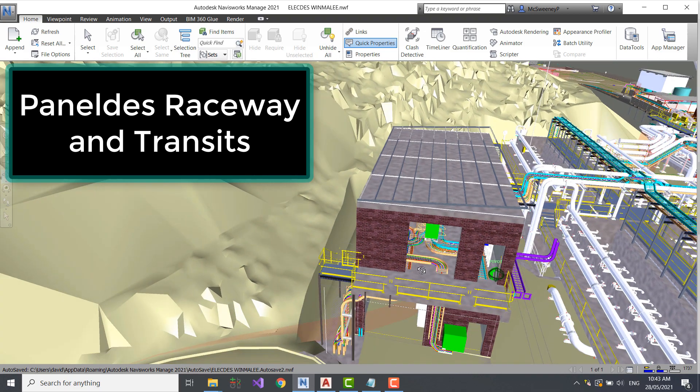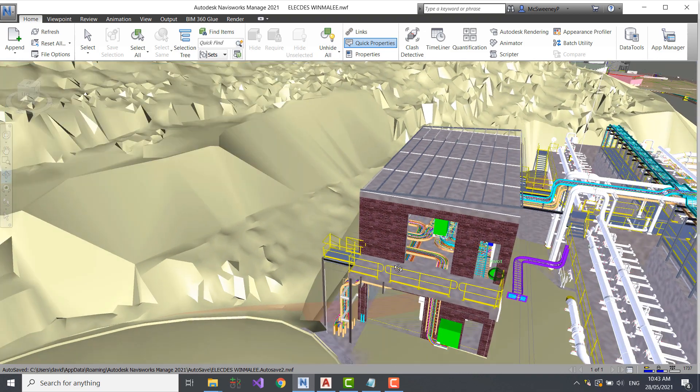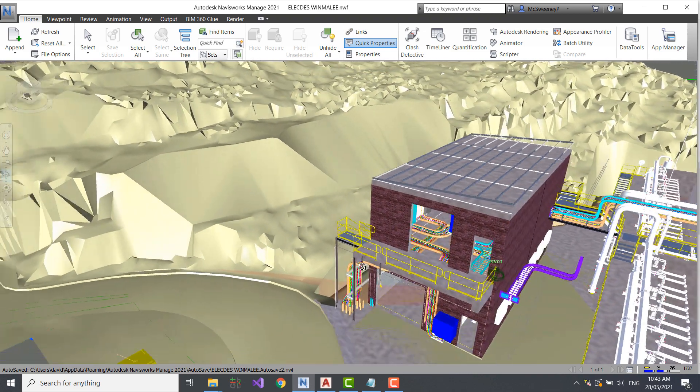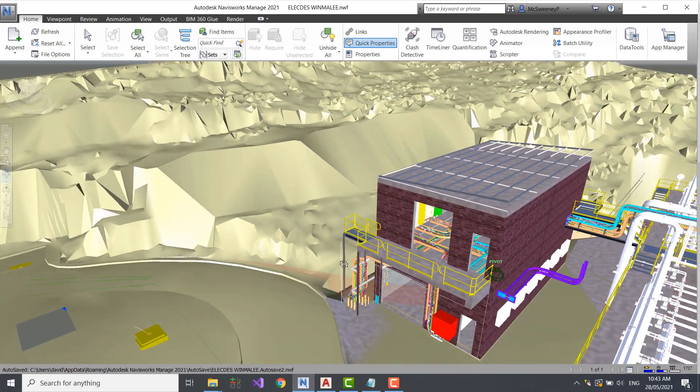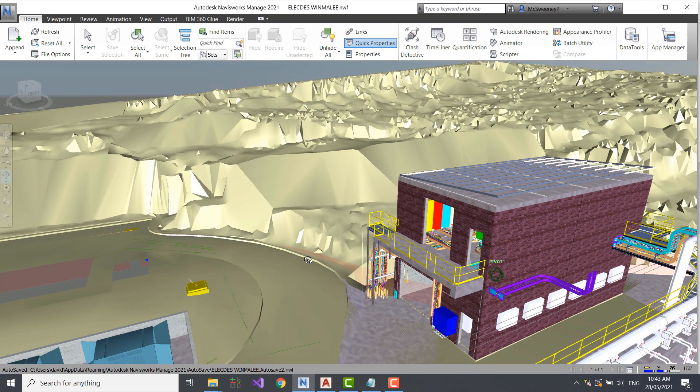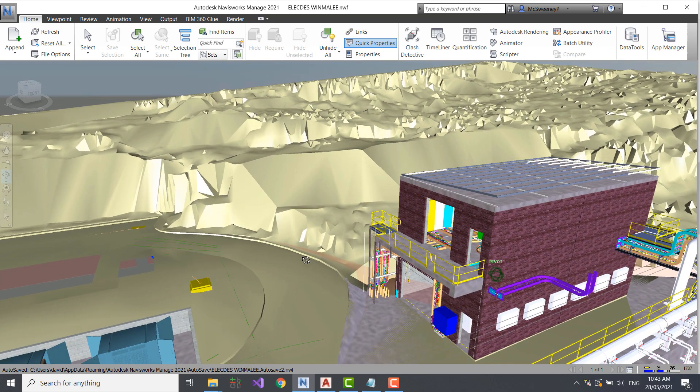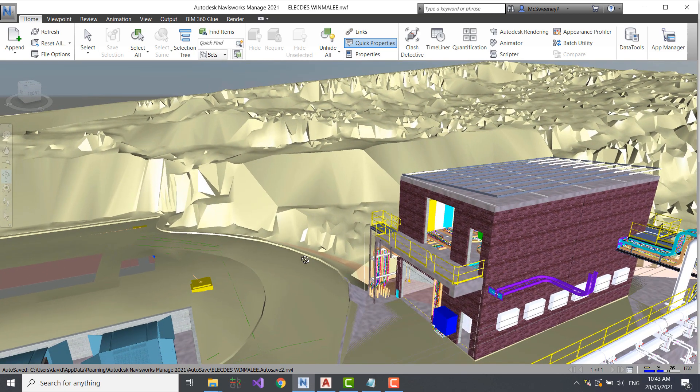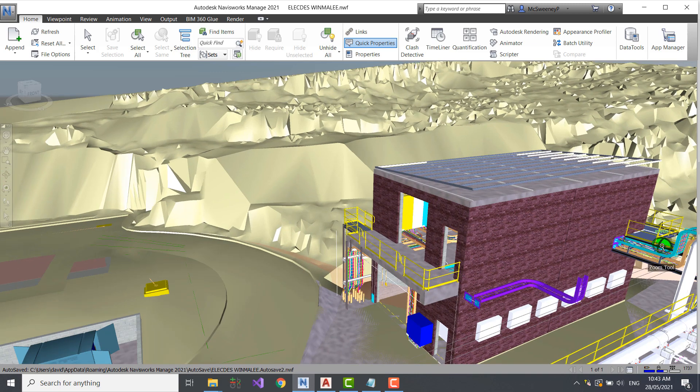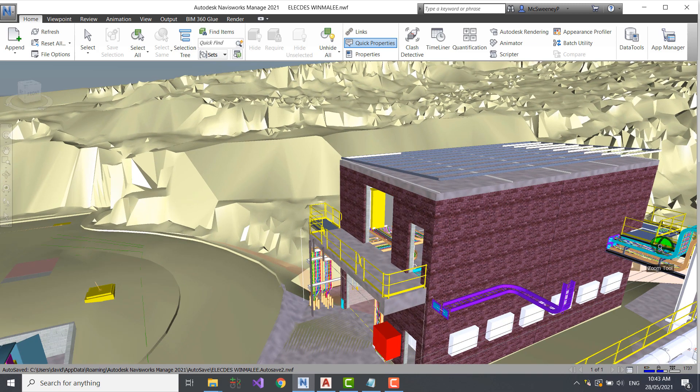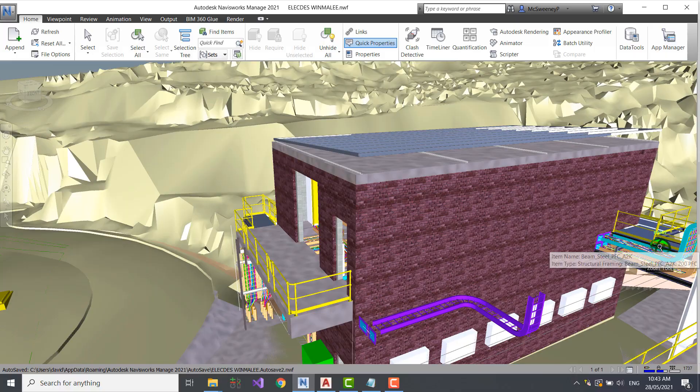Transits are Raceway components providing penetrations through walls, bulkheads and cabinets for multiple cables, while keeping out penetrants such as water, air, gas or fire. Transits provide a cost-effective, flexible and efficient alternative to most gland plate designs.